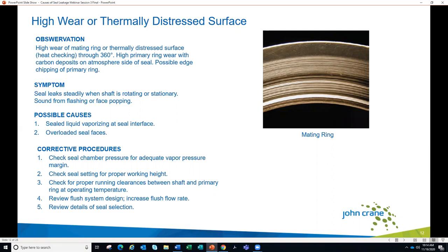You might hear sounds of popping or flashing occurring at the seal interface — this tells us the fluid lubricating the seal is vaporizing between the faces, going from liquid to gas and no longer providing enough lubrication. We're seeing heavier contact, higher heat generation, and heavier wear. This can also occur if the seal faces are overloaded — not installed at the proper working height, with insufficient flexibility of the spring mechanism behind the primary ring. If seeing this, ensure you're following a good installation procedure or switch to a cartridge seal where working height is set by the seal manufacturer. If liquid vaporizing is the concern, review the support system to make sure adequate cooling keeps the sealed fluid in liquid form and provides good lubrication.